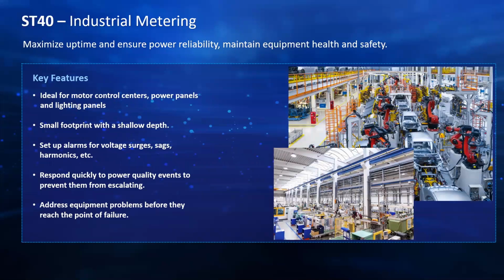Industrial metering, monitoring individual motors is a perfect example. Monitoring assembly machines is a great example. Conveyor systems, those are a series of belts and motors. All of that can cause problems. Using a meter with power quality monitoring capabilities will allow us to view harmonics, waveforms, also to figure out the crest factor or K factor. So we can see if there's bearings on conveyor belts that are starting to go bad or motors that are starting to go bad. We can take preventative measures as opposed to reacting to the piece of equipment failing.